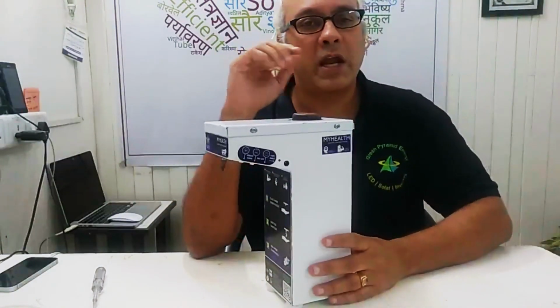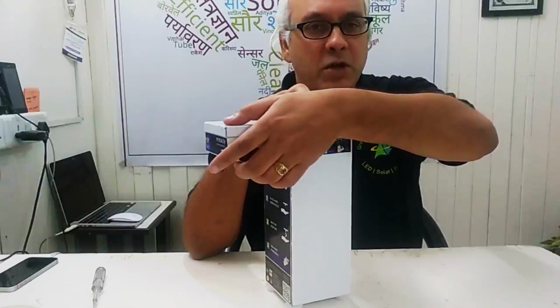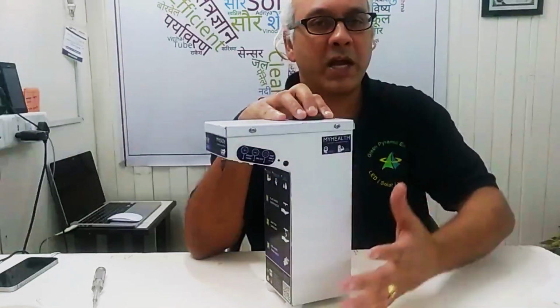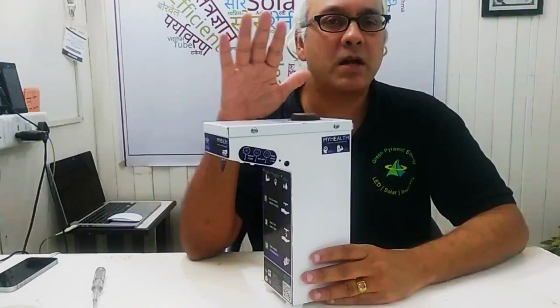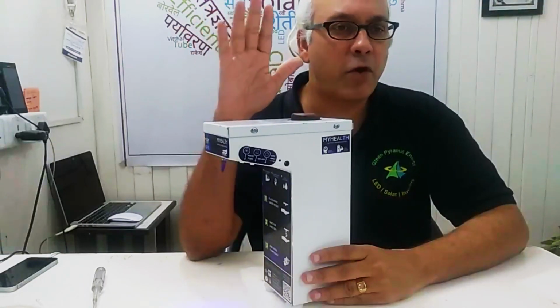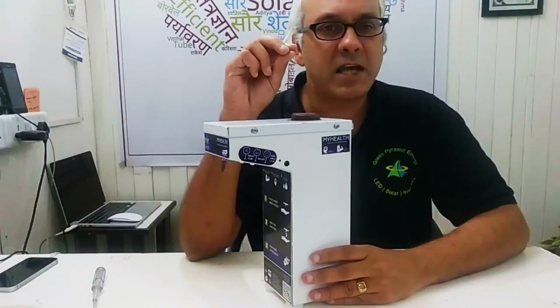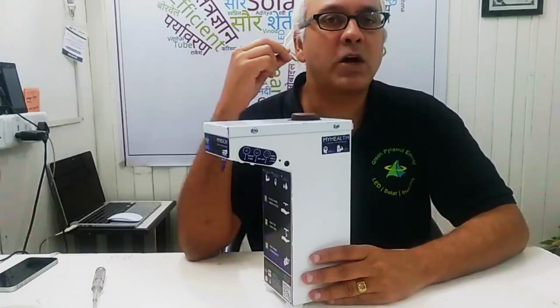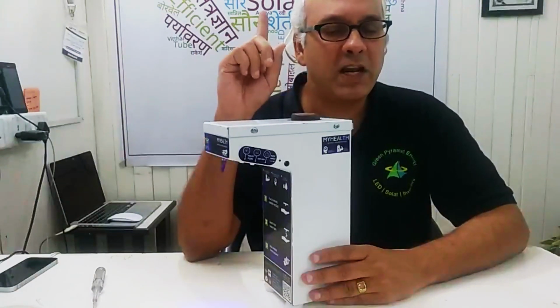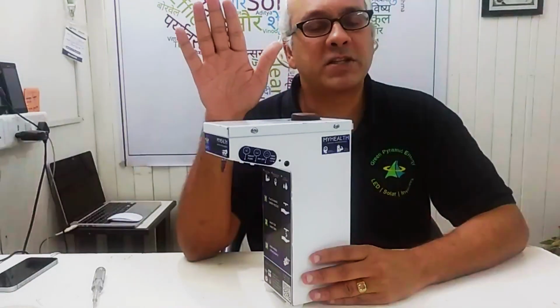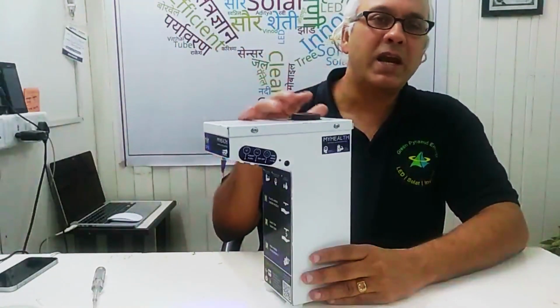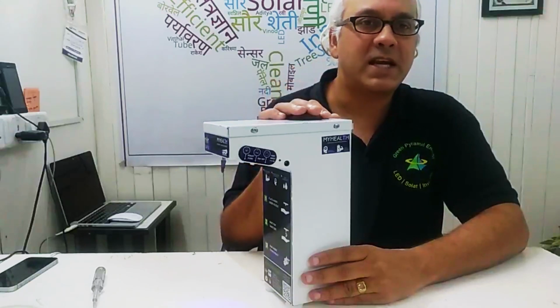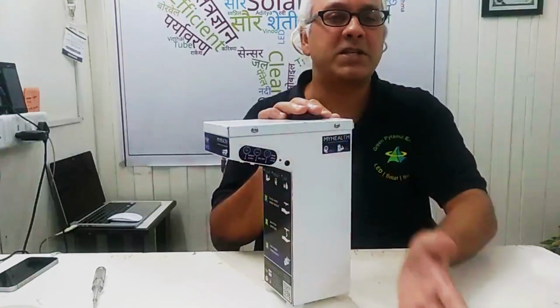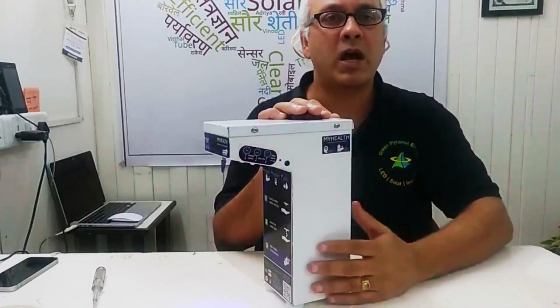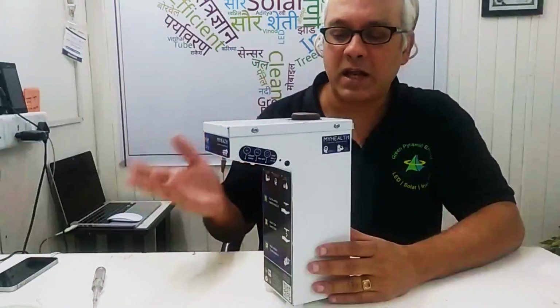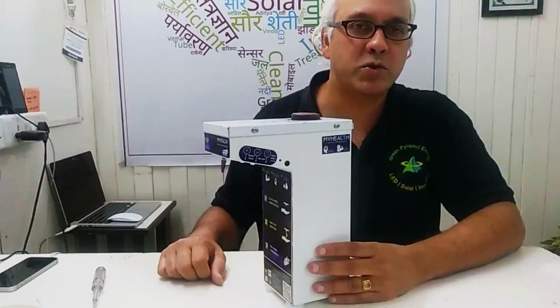Other thing to note is if you come into the calibration mode by pressing both the buttons together, and you leave the machine in that same mode without adjusting anything for about a minute, there is a safeguard where the machine will come out of the calibration mode by itself. You will hear a beep and the machine will start functioning properly. Now during adjustment, if you're not happy with the setting, you can simply turn off the machine and then turn it back on again, and then the machine is operating as usual.